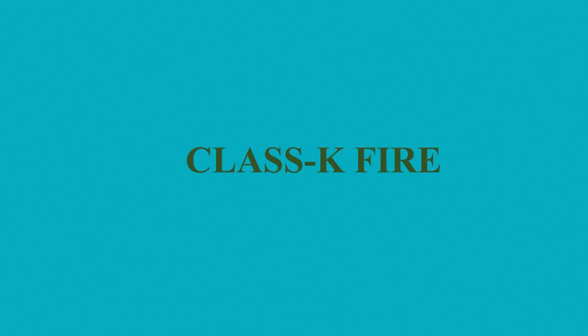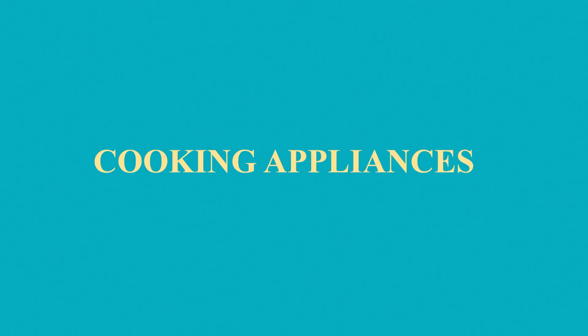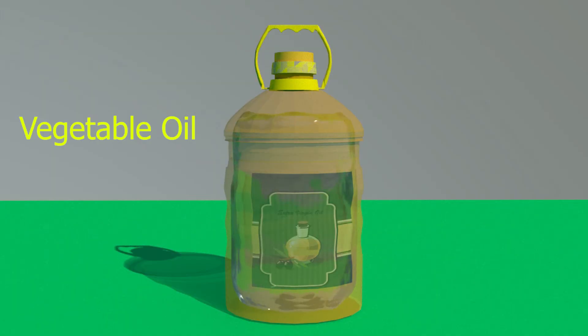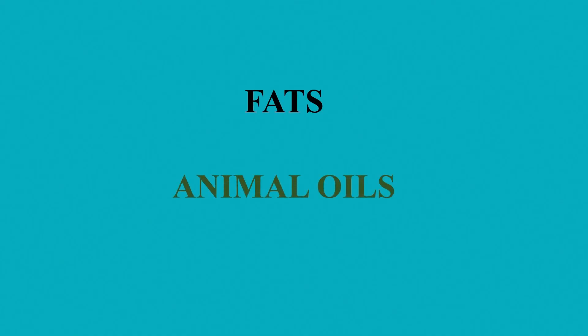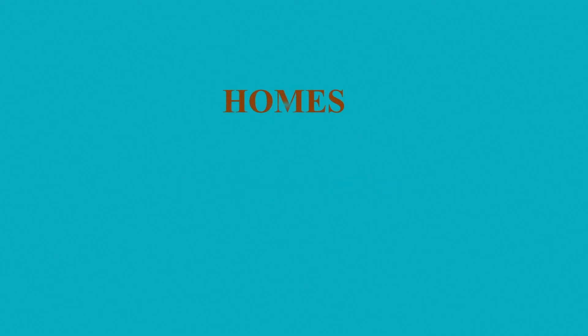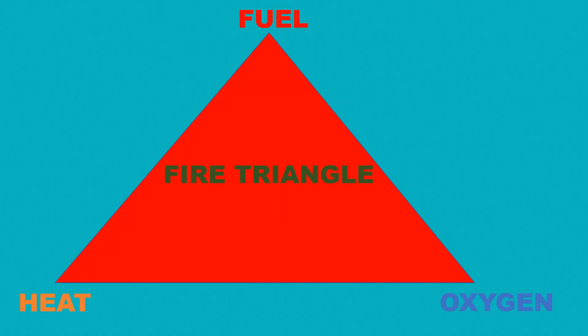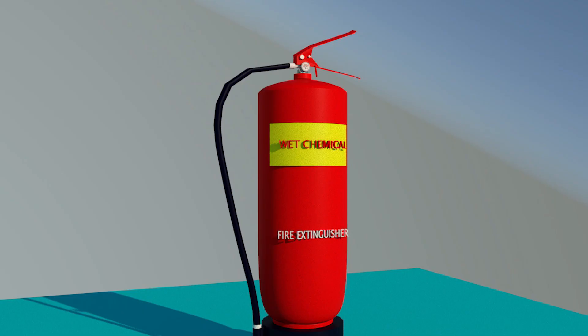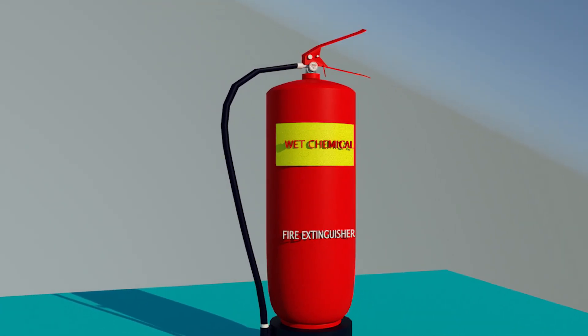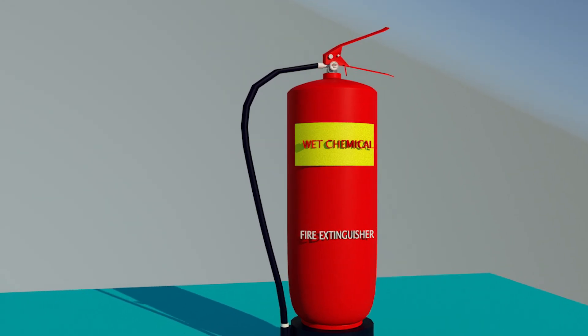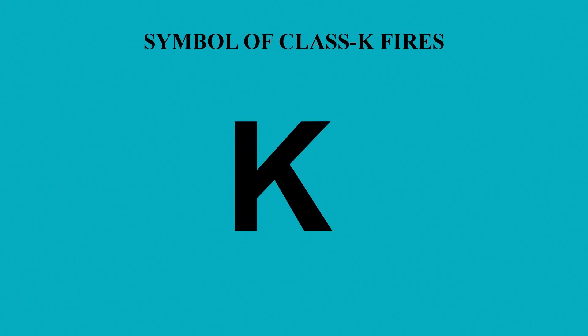Another important type of fires are Class K fires. Class K fires generally occur in cooking appliances that use cooking media like vegetable oils, fats, animal oils, etc. These types of fire commonly occur at homes or restaurants. These fires are extinguished by cutting the heat element of the fire triangle. Wet chemical powder is used to extinguish such fires. These extinguishers are identified by the symbol capital letter K.